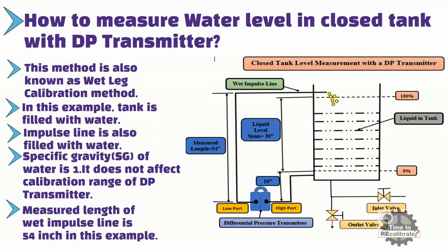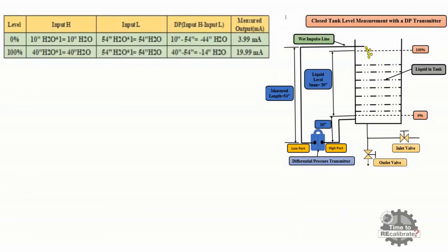As you can see from the table, at zero percent level, the DP transmitter high side has 10 inches H2O pressure, multiplied by the specific gravity of water which is 1, giving 10 inches H2O on the high side. Similarly, at zero percent level, water in the wet impulse line puts 54 inches H2O pressure on the low port, multiplied by the specific gravity of water, giving 54 inches H2O on the low side. Differential pressure is high side minus low side: 10 minus 54 equals minus 44. Hence, differential pressure is minus 44 inches H2O at zero percent level.